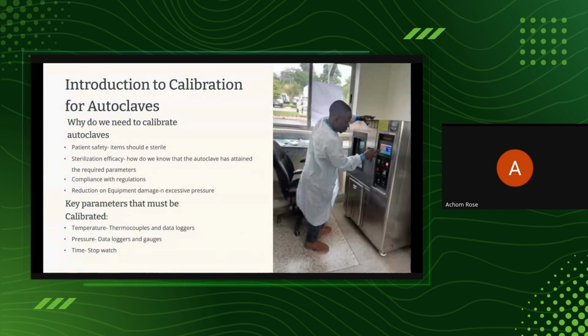Most of the time, these regulations actually work on the negative side: when a patient has a problem, that's when they will come and ask, was this equipment calibrated? Maybe the patient has even taken the hospital to court. Yeah. So now they start looking at the equipment, and unfortunately, they find that the equipment was not calibrated. That is the first thing that they will consider. However much you serviced and maintained, you have a PPM schedule that you follow, once the equipment was not calibrated, it becomes non-compliant to the regulations.